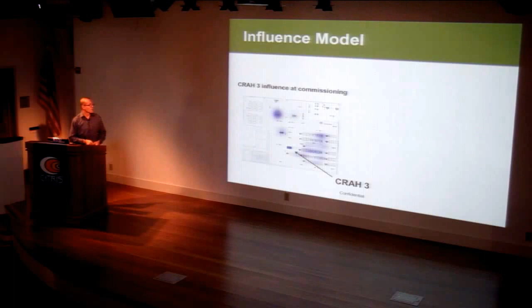Now, this demonstrates its ability to learn here. So what happened in this data center is that the customer, about 6 weeks after we put this in, went and put in containment in this high density part of the data center, so that the hot air discharged from these servers gets captured in that hot aisle, routed up over the ceiling, and back down into 4 of the 12 air conditioners on this floor. The idea there is to not mix hot and cold air for efficiency purposes, and that in fact did work.